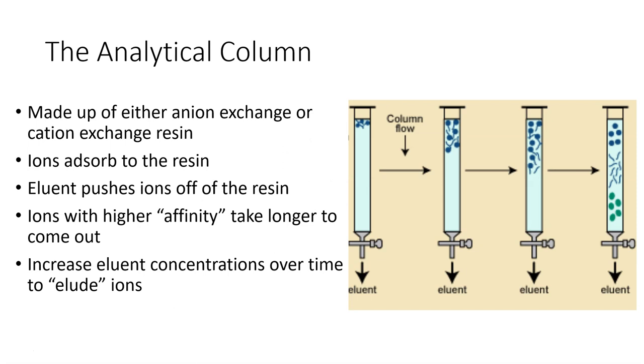The analytical column is the heart of ion chromatography. It's made up of either anion exchange or cation exchange resin. This causes ions to adsorb to the resin, and then eluent pushes the ions off of the resin. Ions with a higher affinity will take longer to come out. What this affinity means is how stuck to the resin is this ion—this has to do with the ion's charge, its size, its electronegativity, and some other things. Basically, the harder something is stuck to that resin, the longer it's going to take to come out.